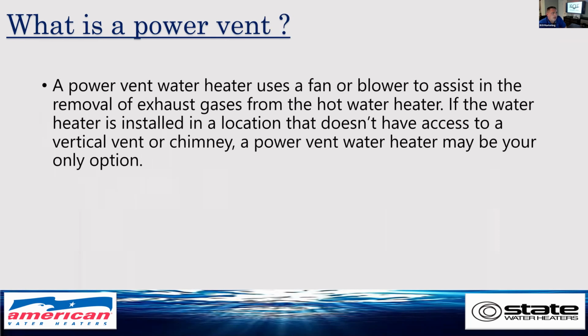So what is a Powervent water heater? A Powervent water heater uses a fan or blower to assist in the removal of exhaust gases from a hot water heater. If the water heater is installed in a location that doesn't have access to a vertical vent or chimney, a Powervent heater may be your only option.